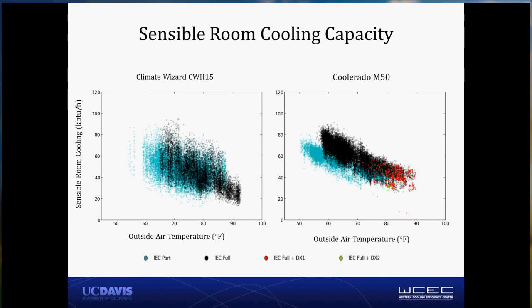It's also important to remember that we've applied this equipment to provide for all of the ventilation in the space. Under all conditions that we've experienced, they're able to cover the entire ventilation cooling load. So that is, they're able to take all of the ventilation air, even at peak, and bring it down at least to the room conditions, and almost always below the room conditions. When you are supplying air below the room conditions, you're also providing some sensible room cooling. You're affecting the temperature at the thermostat in a positive way.